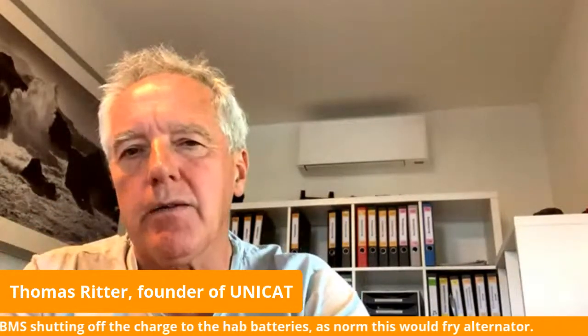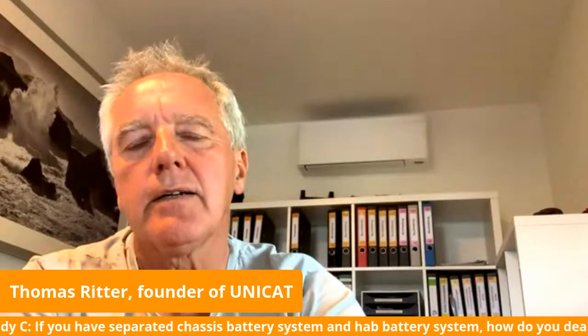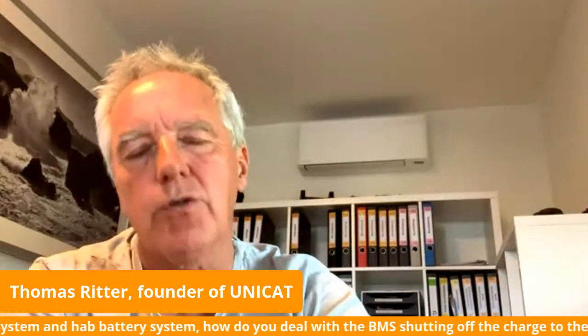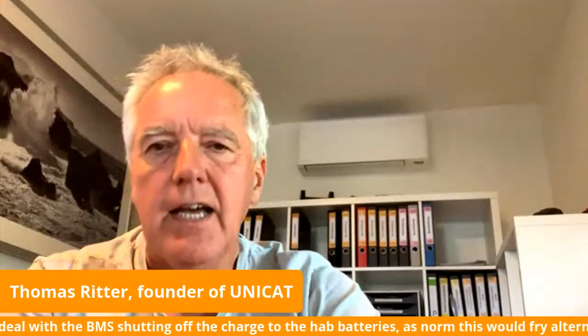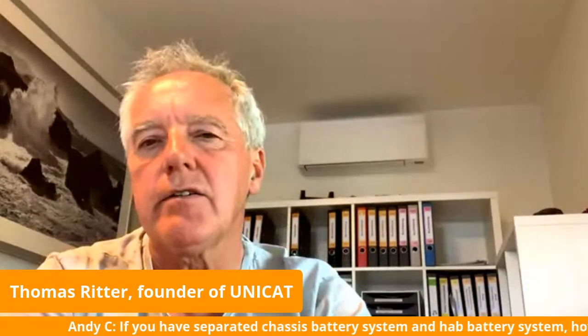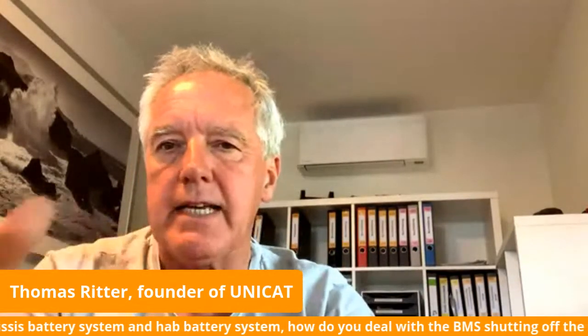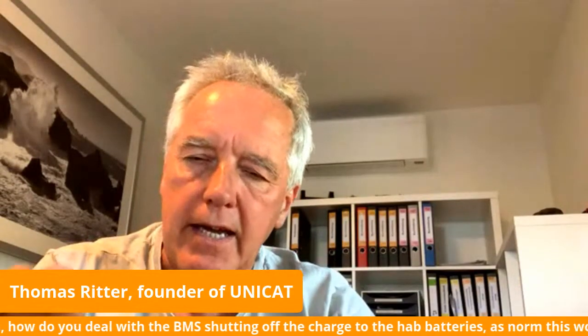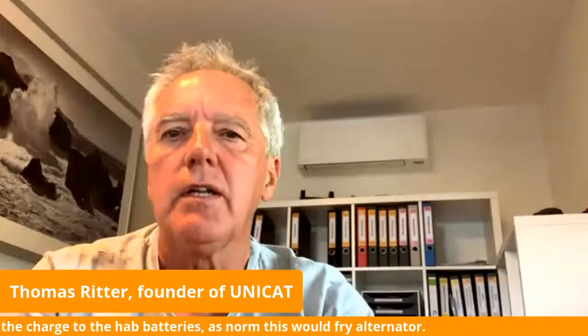So what we use is a device to protect the alternator from these overvoltage peaks. That's a general precaution and it solves the problem. Of course, we don't disconnect the external regulator, but we set the injected voltage to 0 so it's not pushed to produce higher amps and higher voltage. So we set the external regulator to 0, and we have overvoltage protection on the alternators.